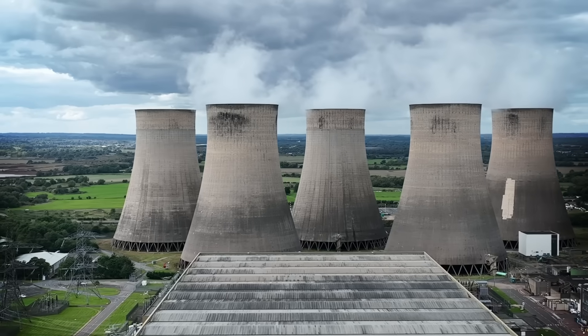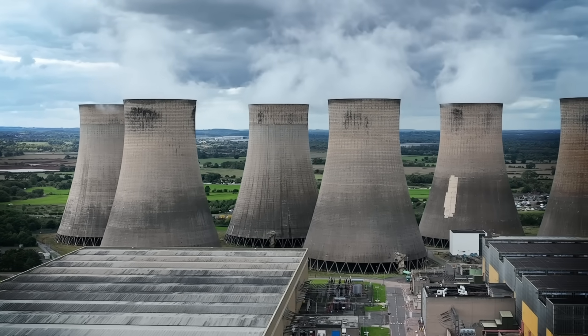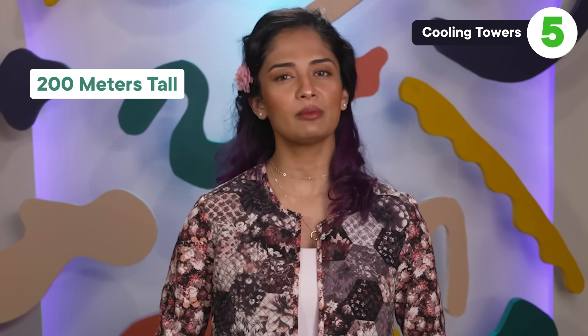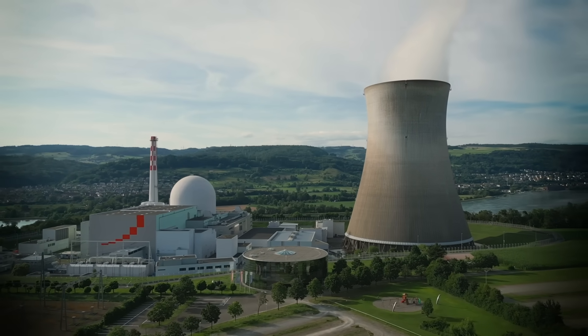Basically, some additional water is piped in to absorb the heat from the water in the steam turbine, and once that new water is hot, it gets sprayed inside the tower where it mixes with the air. As that hot, humid air rises out of the tower, more cool dry air gets pulled in through vents at the base, causing a natural draft of air currents moving up and out. The hyperboloid shape moves air upward better than a cylinder or cone. The wide base helps suck in more cool dry air, while the wide top helps air mix to distribute the heat and humidity. According to mathematical models, the narrow center helps increase the velocity of air whooshing upward. These cooling towers are up to 200 meters tall, and we need them to be sturdy. The hyperboloid is curved in two opposite directions, giving it fewer weak points than a plain cylinder, and the curvy walls help deflect wind and distribute force from strong gusts instead of buckling — a really nice feature when you have a nuclear reaction counting on them.